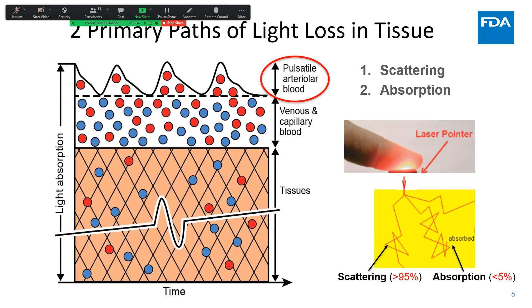And the principle here, if you go to the next slide, Sandy, is that there are different wavelengths of light. You see it at the very top there, one in red and the other in infrared, shown as kind of a light blue and a bright yellow. As it impacts the vessel, as it changes in diameter or volume, it reduces the amount of light that is then detected on the other side. This is a typical finger-based sensor, so this would be a transmittance or transillumination style. But you can see that attenuation is also there because of those wavelengths, and each wavelength is impacted differently depending upon the color of blood. So this makes up the second estimate of what this thing is supposed to read out.